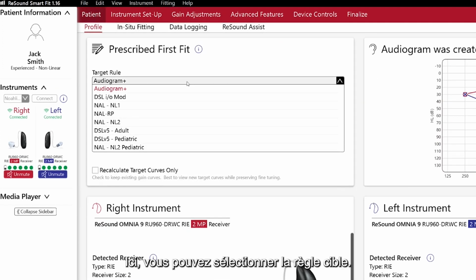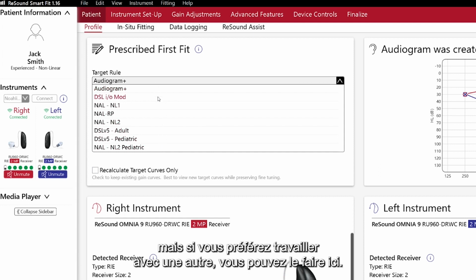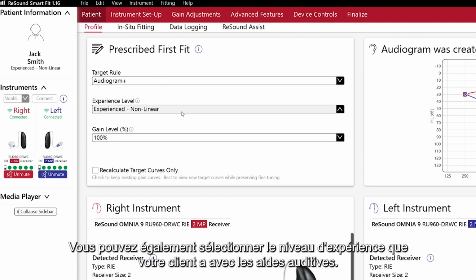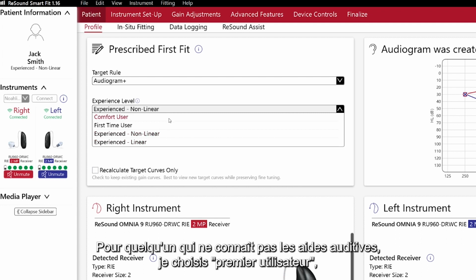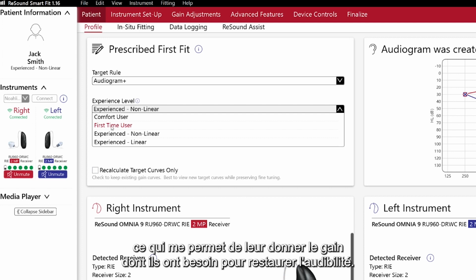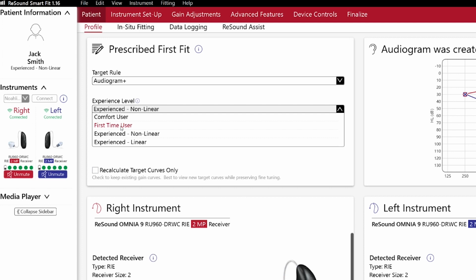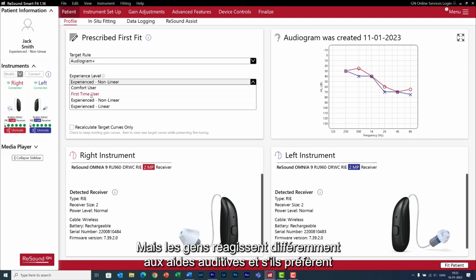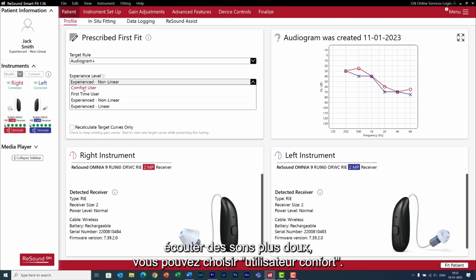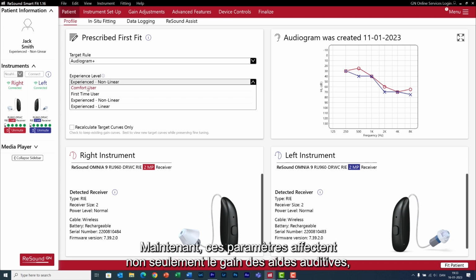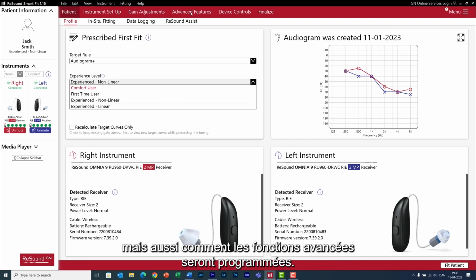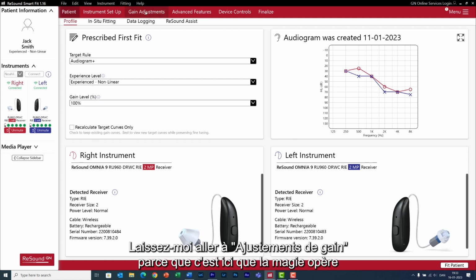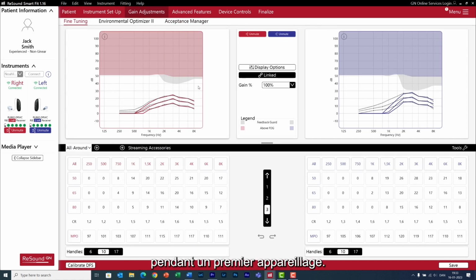Here you can select the target rule. Audiogram Plus is the one for ReSound, but if you prefer to work with a different one, you can do it here. You can also select how much experience your client has with hearing aids. For someone who is new to hearing aids, I choose first-time user, which allows me to give them the gain they need to restore audibility. But people react differently to hearing aids, and if they prefer to listen to softer sounds, you can choose comfort user. Now, these settings affect not only the gain of the hearing aid, but also how the advanced features will be programmed. Let me go to gain adjustments, because this is where the magic happens during a first fit.